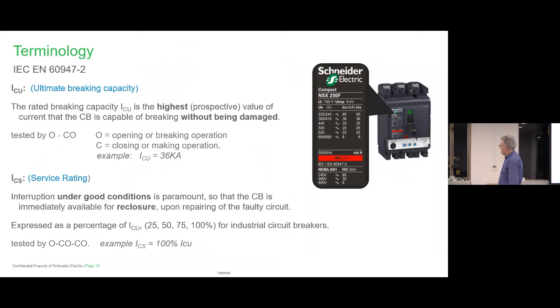But what's even more important is another figure here, where it says ICS. That's the service rating, or what I would call the safety rating of the breaker. It's saying this breaker can see the maximum ICU value, 100%. This is 100% because it says 36 and 36, but you might have 36 and 18 here, or 36 and less than 18. And that means open, close under fault, open, close under fault, open, and the breaker is still safe.